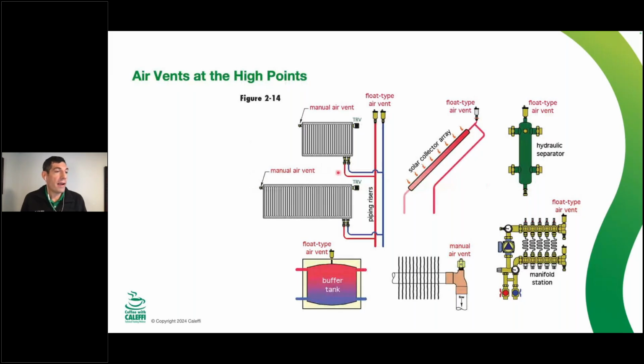So an air vent is something that's going to get air out of a system at the high point. It isn't going to send the air to the high point. That's what an air separator does. An air vent is just something that's going to let the air out if it has accumulated at the top of something. That's why you'd see an air vent on a riser, solar panel, top of a separator, top of this manifold right here. That's where the air is going to go just because it's more buoyant than the fluid that it's in, the water and glycol mixture or whatever.